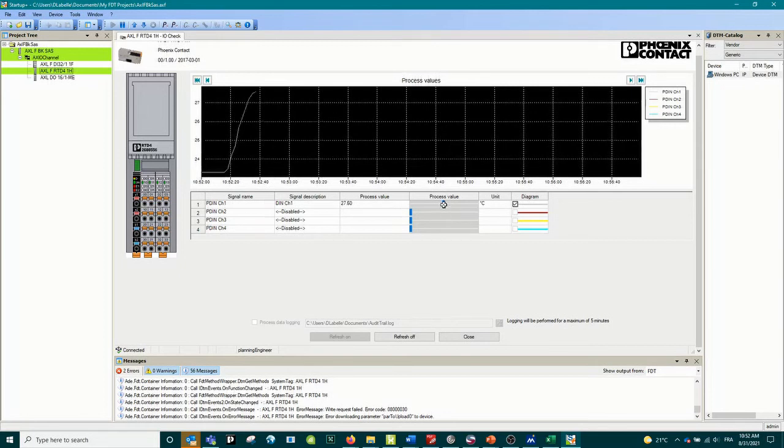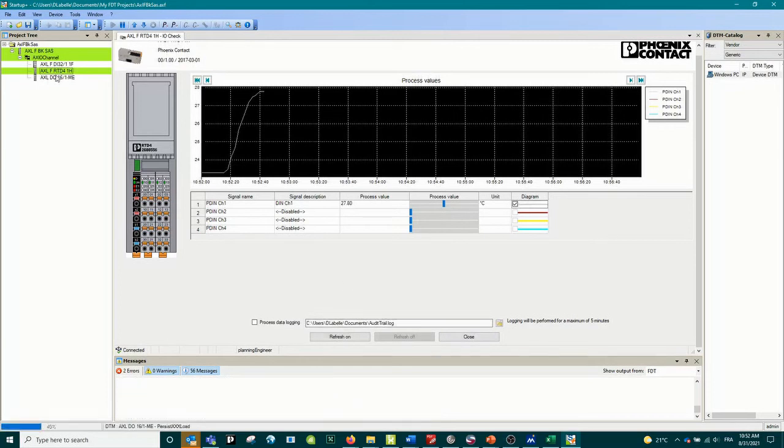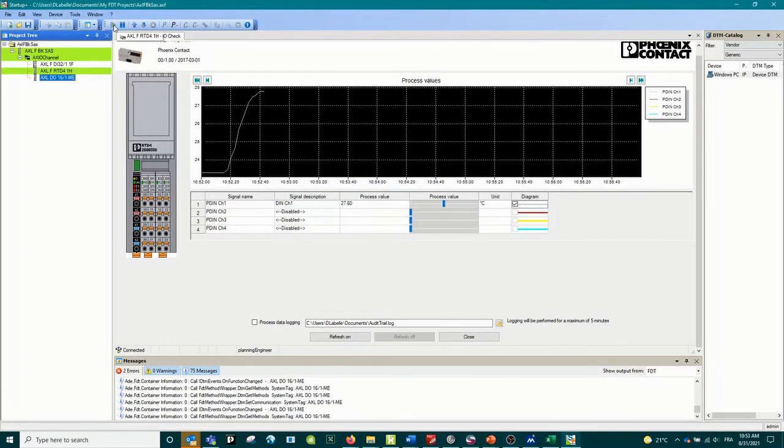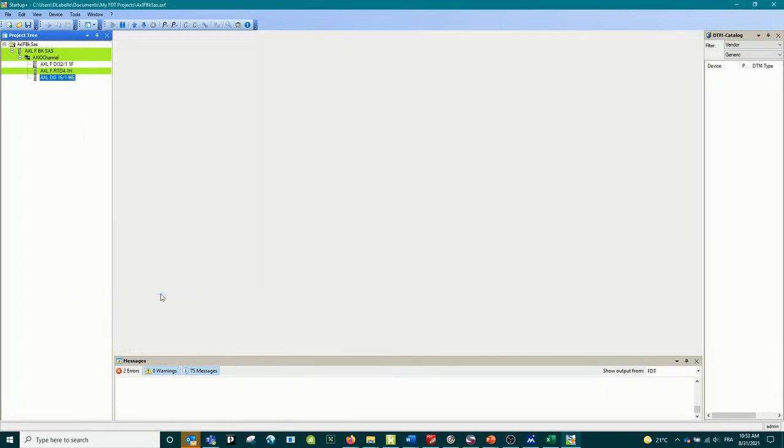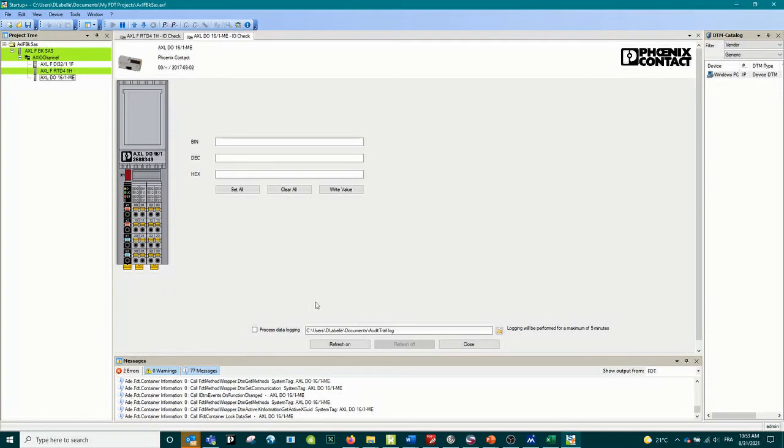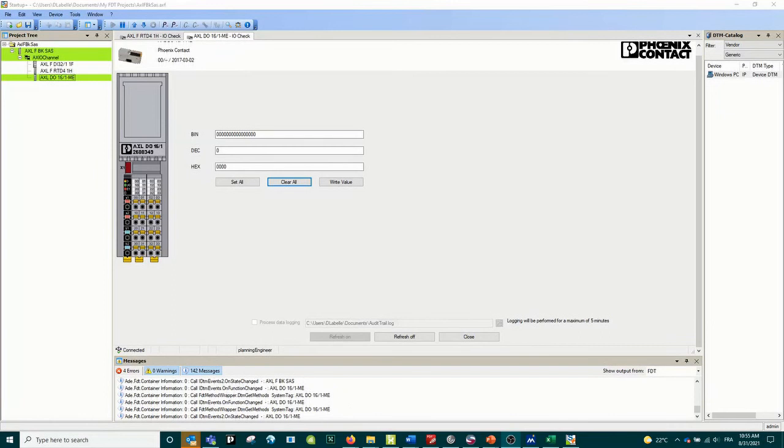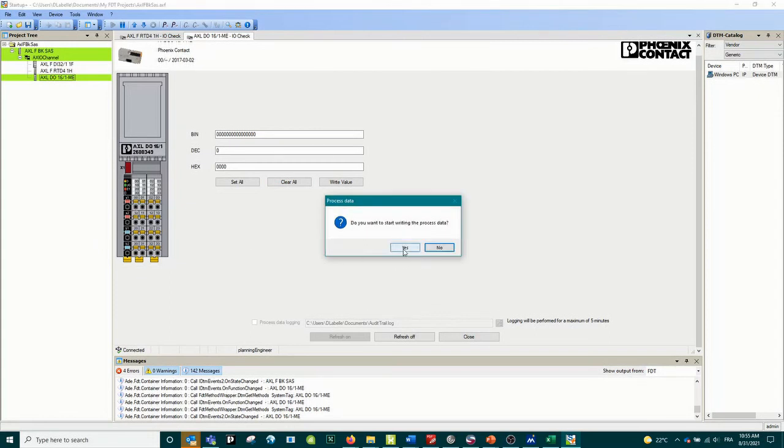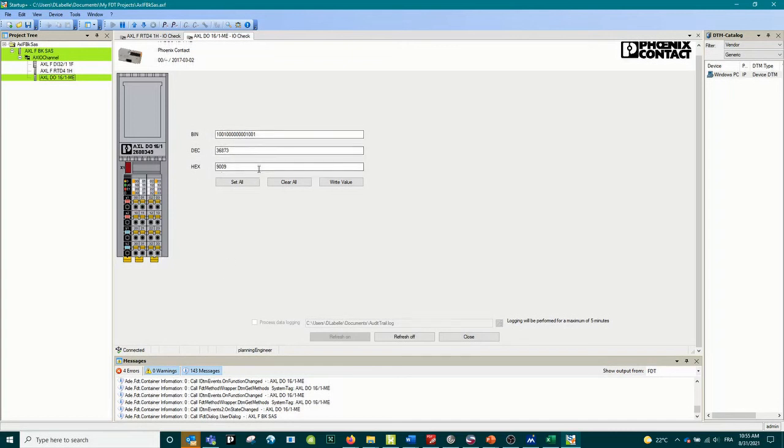You will have the exact same thing using the analog input, and on the analog output you can drive the actual output using those process bars over here. We're just going to press refresh off and connect to the digital output 16 output card. We click on the digital output, press connect, right-click, function IO check. I'm just going to press refresh so it's going to connect to it. Now that we are in refresh function we are able to see in binary, decimal and hexadecimal. I just have to - as you can see there is a small N - I just need to click over here. Would you like to force the output? Yes. I just need to click which output I would like to force and it's going to force it. You can force it using binary, decimal, hexadecimal, you can write a specific value.